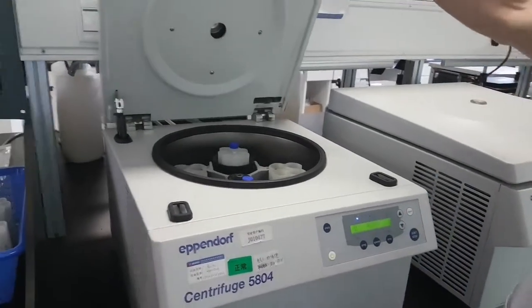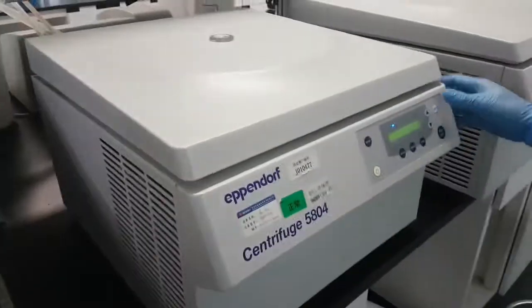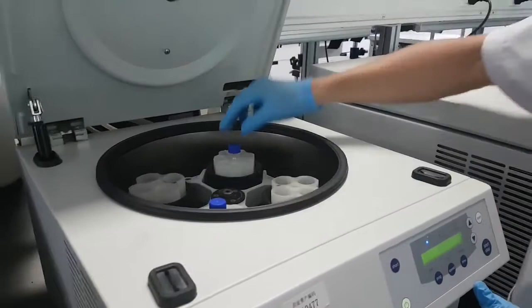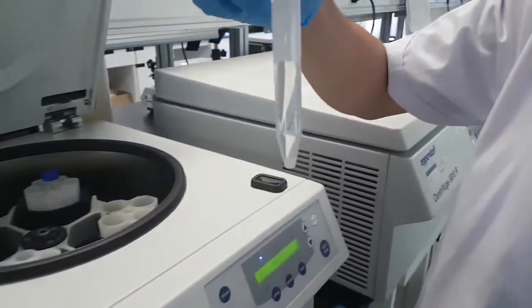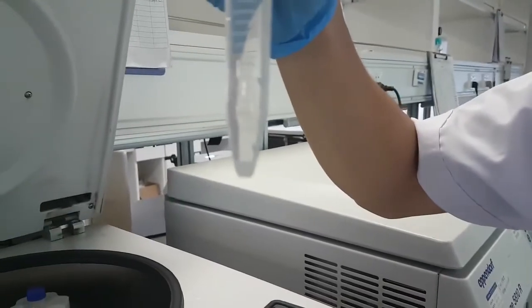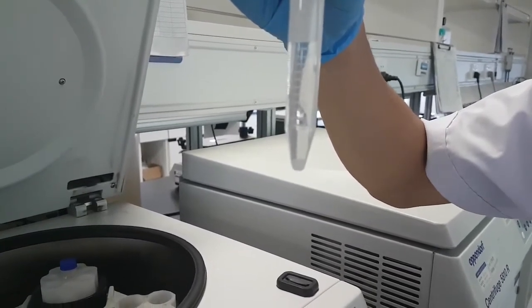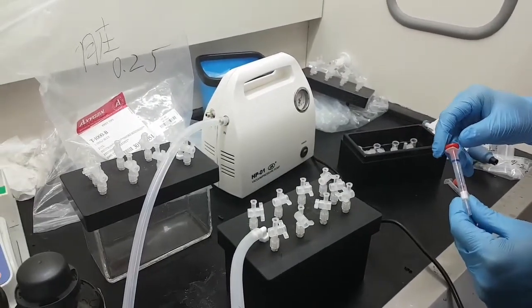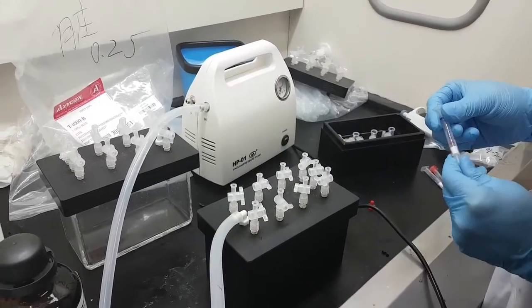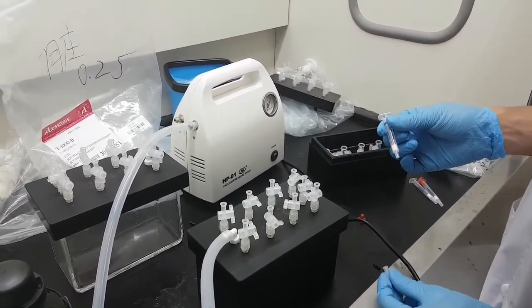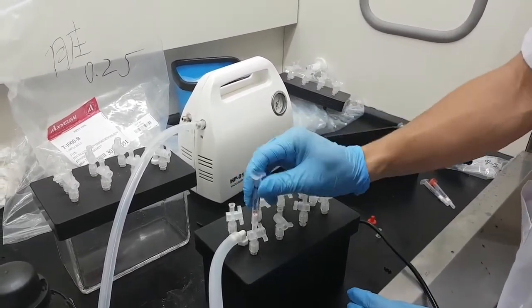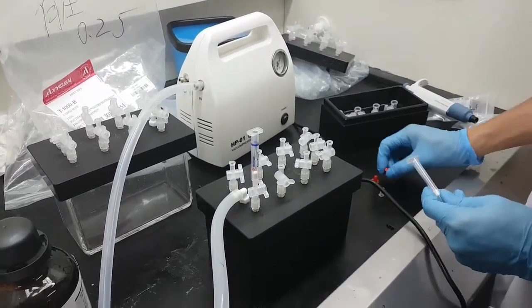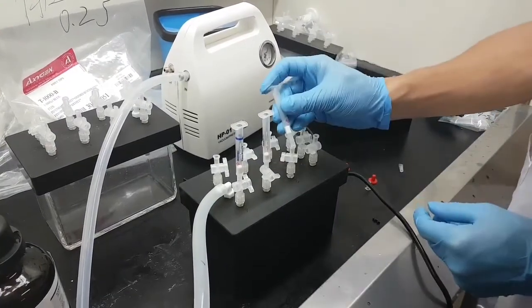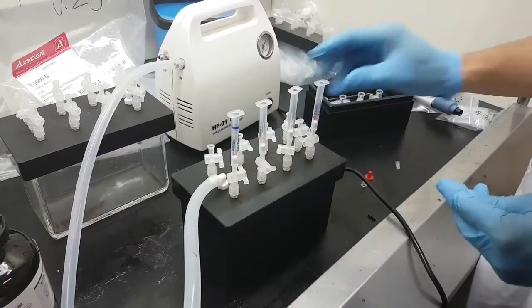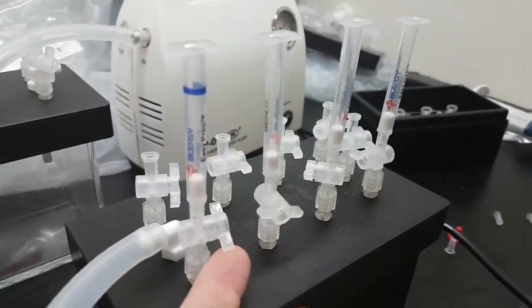Centrifuge for 1 minute at 4000 RPM. Take out, and we'll find here a little bit of sediment. Next step will be sample extraction. So for sample extraction by instrument, first thing we do is connect the extraction units. We have 4 extraction units. Pay attention that the columns are placed this way.